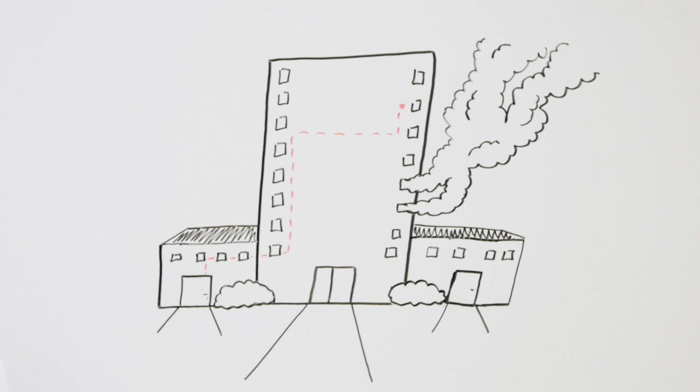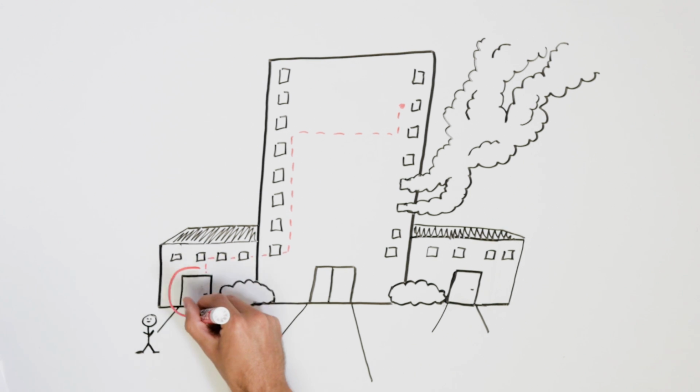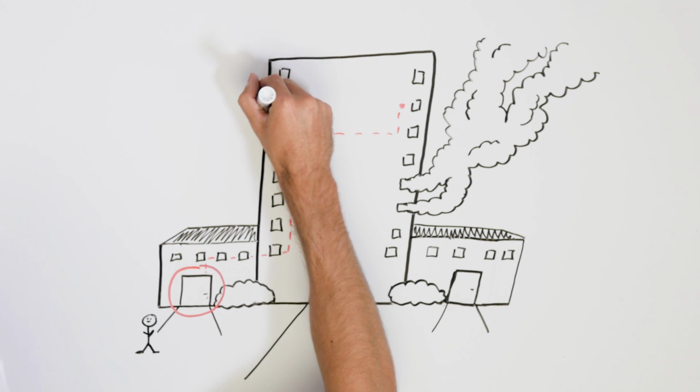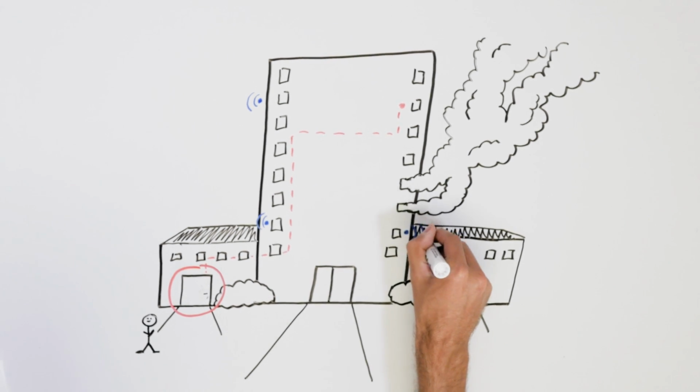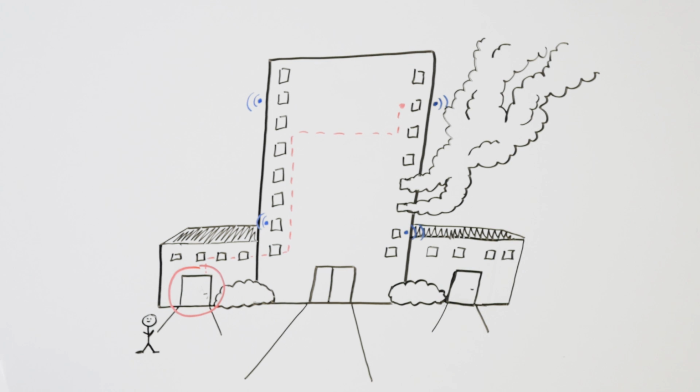The International Building Code, or IBC, requires interior stairway means of egress doors to be openable from both sides without the use of a key or special knowledge or effort, with some exceptions. The discharge door can be locked on the outside, but must allow free egress. Many interior stairwell doors are locked on the stair side to prevent unauthorized access to the floors of the building. For these doors, the IBC requires electrified locks which can be unlocked simultaneously upon a signal from the Fire Command Center or from another approved location.